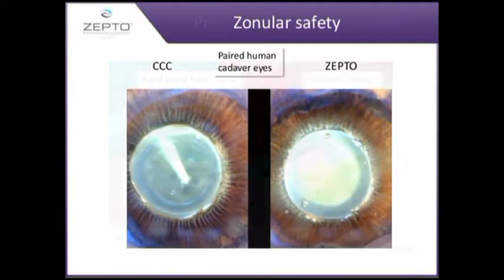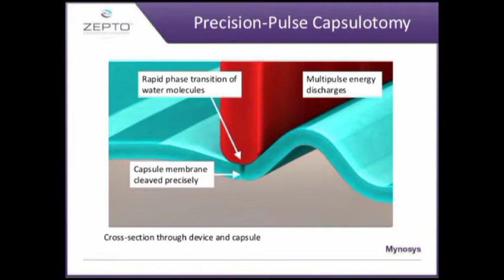This is a Miyake Apple view, and during video studies it has been found that there is no stress while creating these capsular rhexis on the zonules. So this is the basic technology. When the nitinol ring is pressed against the capsule and suction is applied, nanopulses of energy are delivered, and these rapid pulses of very low energy cause vaporization of the water molecules trapped between the capsule and the nitinol ring, and this creates the smooth capsulotomy.